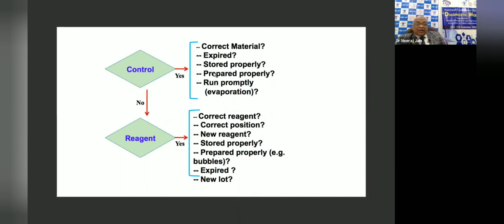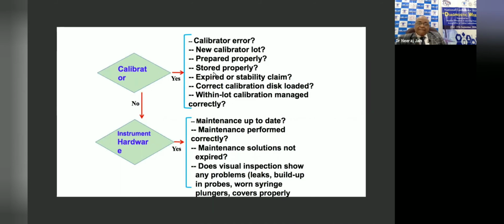If the control material is okay, then look at the reagent. Whether you have placed the correct reagent at the correct position, or if it is a new reagent, you have performed lot acceptance testing properly. These reagents are stored properly. Yesterday we discussed the advantages of onboard cooling. If it is onboard cooling, it is okay. Otherwise, these shall be stored in the refrigerator properly, and there are no bubbles in the reagent. These are not expired. If you are using a new lot, you have performed lot acceptance testing. Calibrator: it is not expired, and if some reconstitution is required, it is reconstituted properly. You are loading these calibrators at the proper position, and you are noting down all data related to the calibrator, and after this calibration, you are checking your machine with the controls and getting control results within acceptable limits.